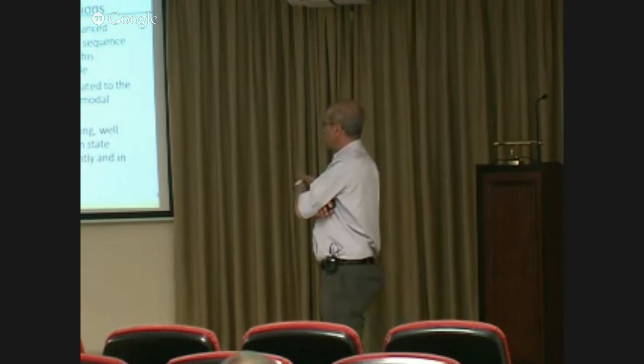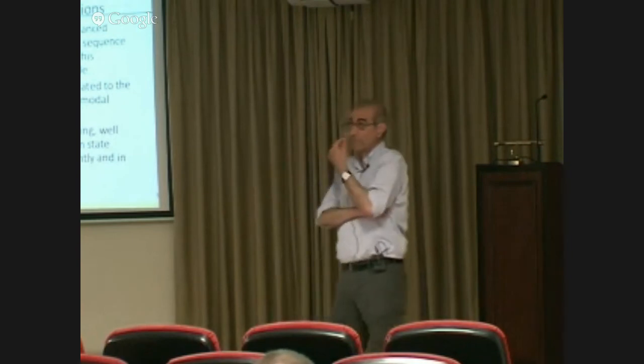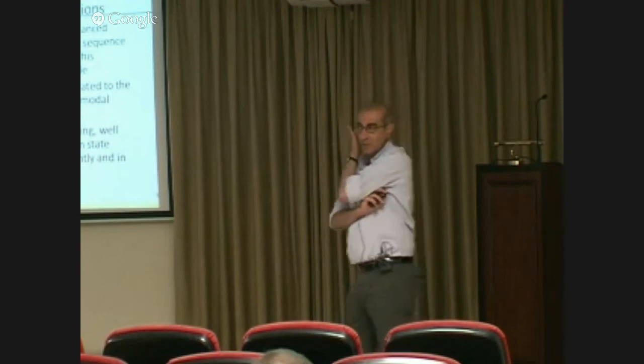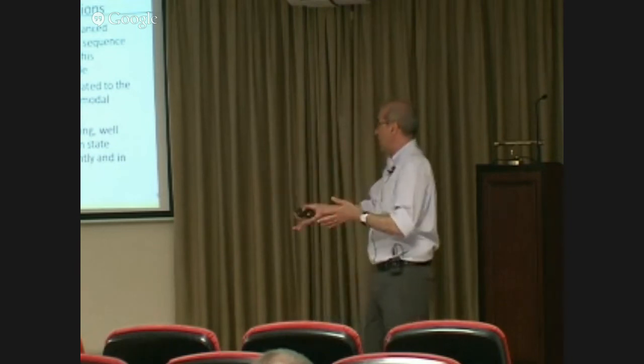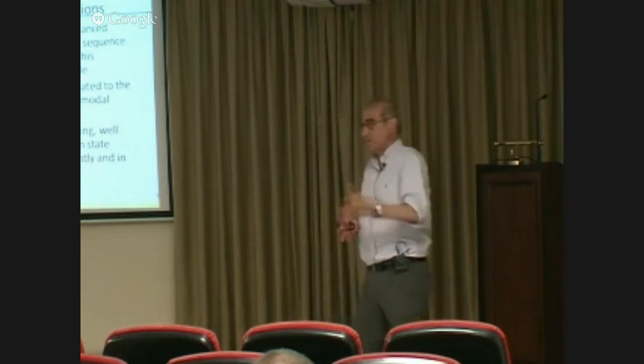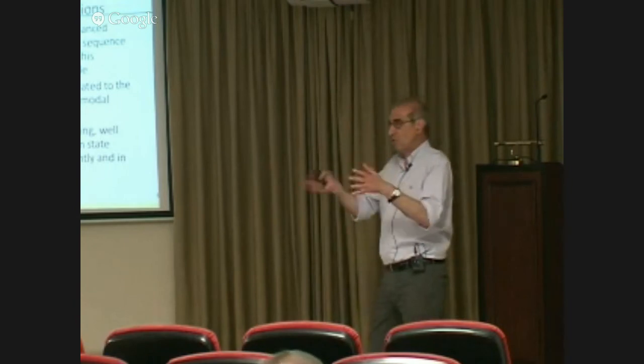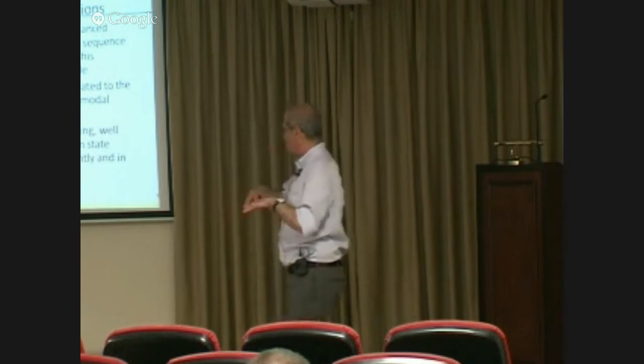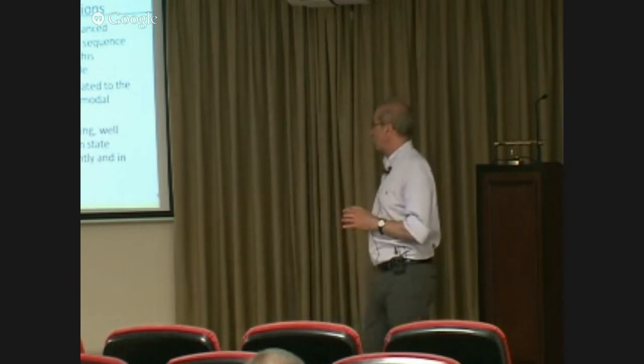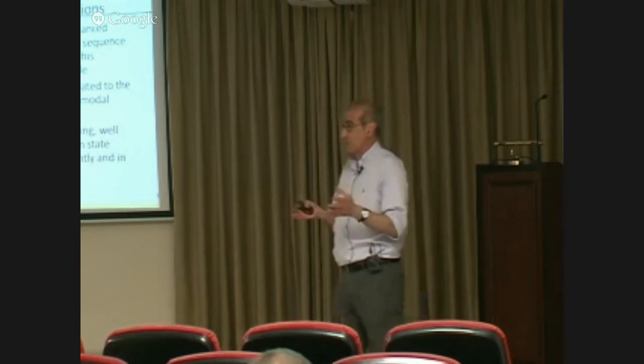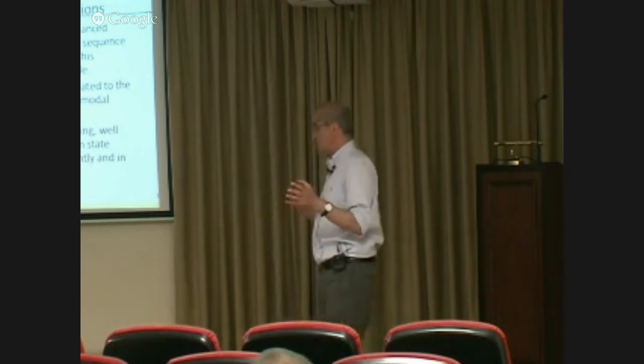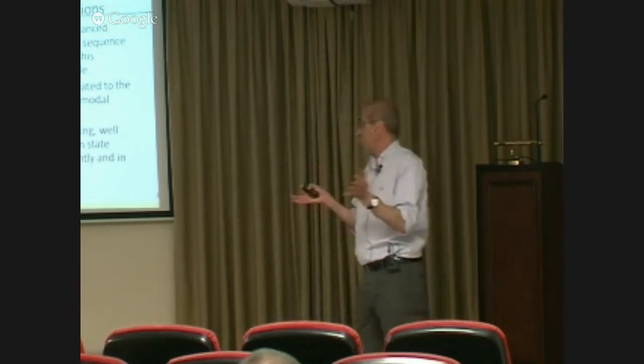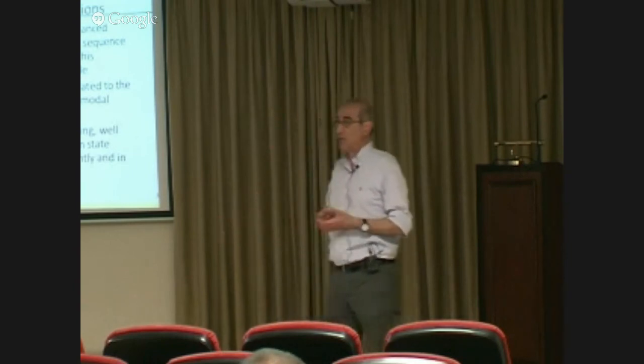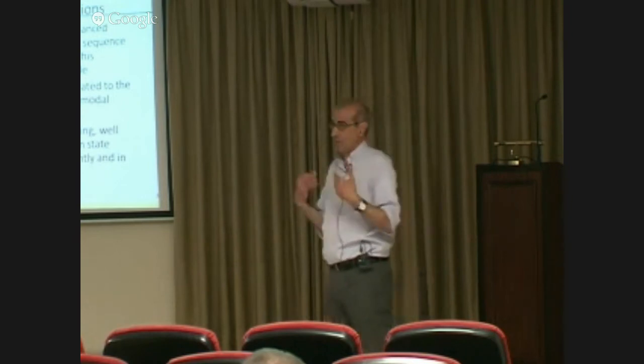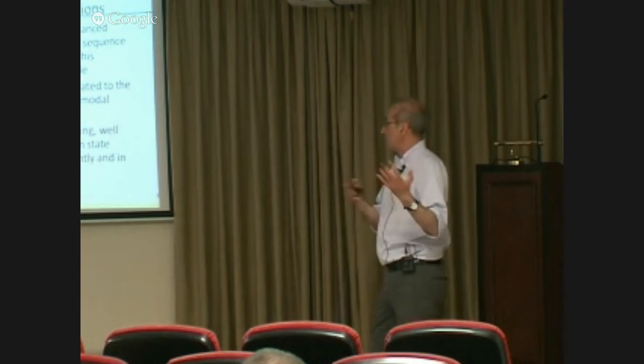Before discussing this, I'd like to bring up fault analysis, which I'm sure most of you know. In fault analysis we use linear equations: V equals ZI, where Z is the bus impedance matrix, I is the injected currents, and V is the bus voltages. We manipulate this linear equation to get a sequence-based, or sequence domain, solution for fault analysis. So if you have an unbalanced fault, you can solve the problem in the sequence domain and then bring the solutions back to the phase domain. The reason we can do this in fault analysis is because the equation is linear, so we can apply this linear transformation to go to the sequence domain and back.